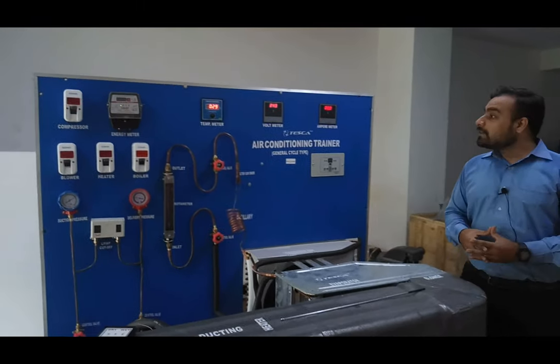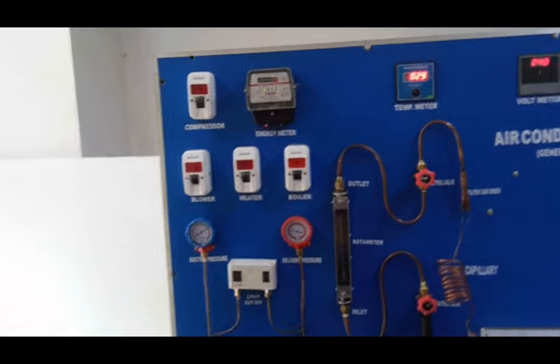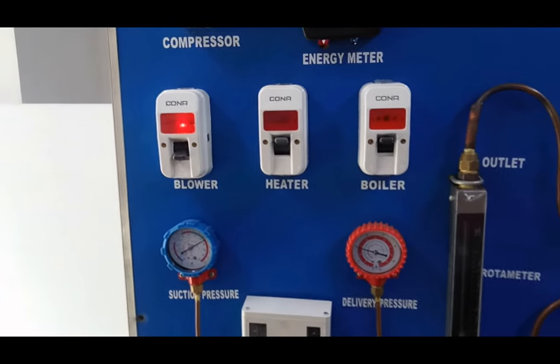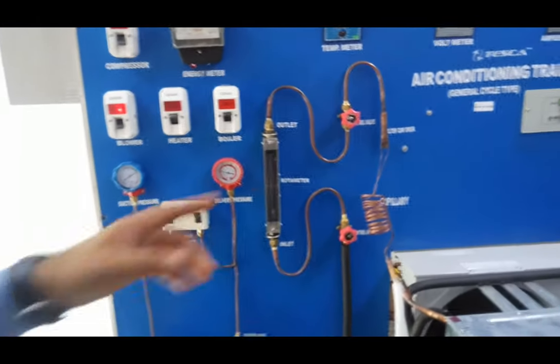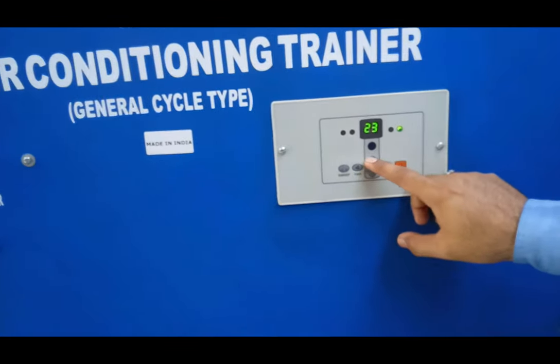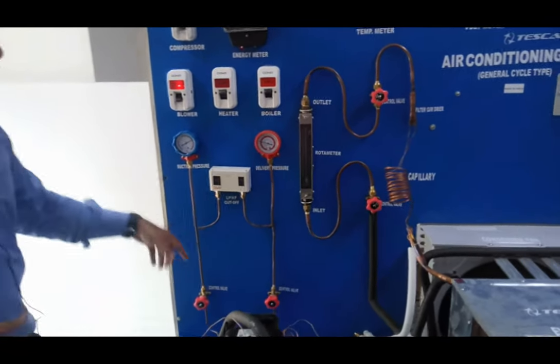Now we start the kit with this on-off button. To start this cycle we first switch on the compressor unit and blower. After reaching the set pressure, the compressor will automatically start in a few minutes. On the control panel we can see the temperature is set at 23 degrees. We can increase or decrease the temperature with these buttons. We will set the temperature at 25 degrees. When the pressure is suitable the compressor will start running. Before starting the unit, make sure all the control valves are opened.